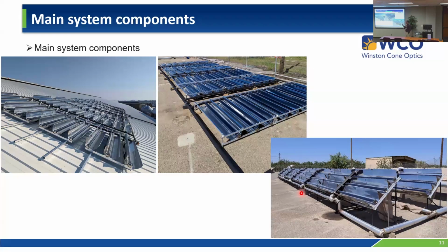The higher the flow rate, the lower the temperature. The less flow rate, the higher temperature you can achieve. Did I say that wrong? The higher flow rate gives less temperature - it goes the opposite way. The less flow rate, the higher temperature you can reach.